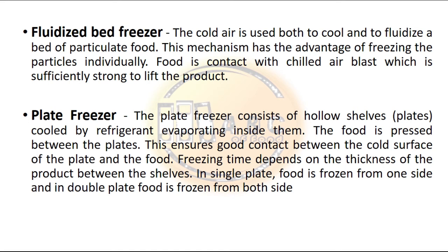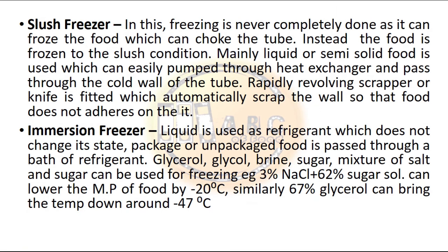Freezing time in the plate freezer depends on the thickness of the product between the shelves. In the single plate freezer, food is frozen from one side; in the double plate freezer, food is frozen from both sides. In the slush freezer, freezing is never completely done, as full freezing could choke the tube. Instead, the food is frozen to a slush condition, and mainly liquid or semi-solid food is used, which can easily be pumped through a heat exchanger and passed through the cold wall of the tube.